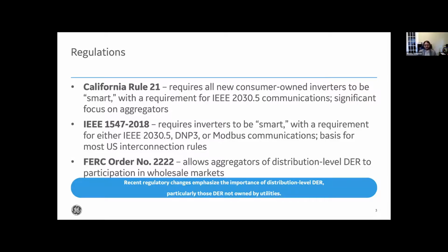There's also IEEE 1547, which has been around for quite a while -- probably the closest thing we have in the U.S. to a federal interconnection standard. In its most recent revision, it requires inverters to have communications capability, listing one of three standards: IEEE 2030.5, geared more toward residential consumers; DNP3, usually more focused on utility-owned assets; and Modbus, usually used for local communications to connect with a gateway. I say usually because all of these can get quite complex.